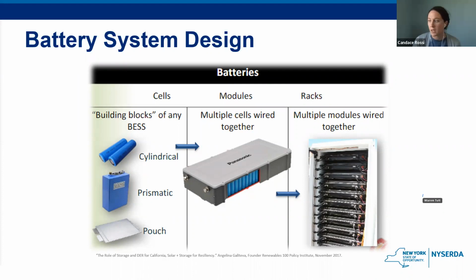And when you start stringing cells together, that's when you get what's considered a module. And then when multiple modules are wired together, that creates the battery rack. So in the end, the battery racks are really just a bunch of really small battery cells wired together to create this larger unit.